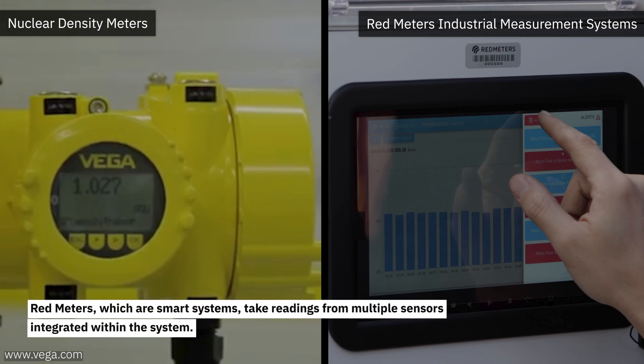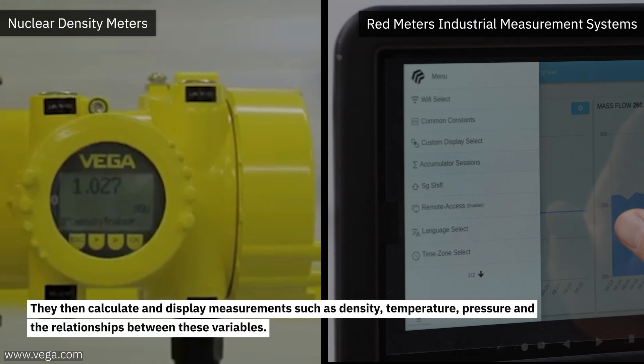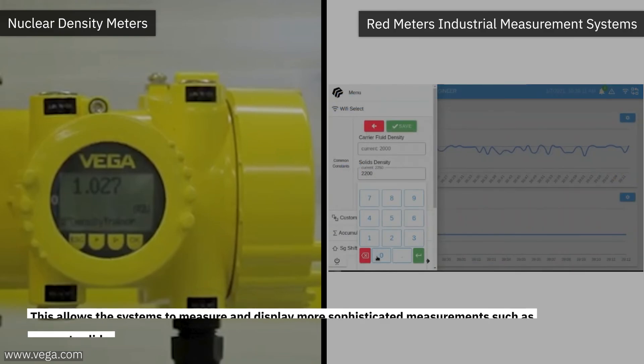Red meters, which are smart systems, take readings from multiple sensors integrated within the system. Then, they calculate and display measurements such as density, temperature, pressure, and the relationships between these variables. This allows the system to measure and display more sophisticated measurements, such as percent solids.